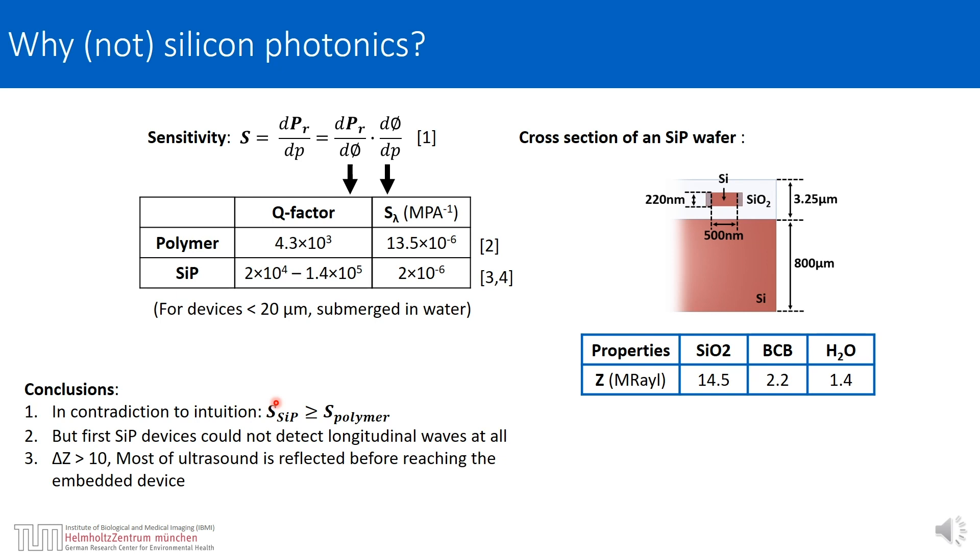The question arises why first silicon photonic structures could not detect longitudinal waves at all, and the reason lies in the design of those structures. Traditionally the silicon waveguide is embedded in a few micrometers of silica cladding. The acoustic impedance mismatch between the silica and water results in most of the ultrasound being reflected from the top surface of the chip before even reaching the resonator and being detected.